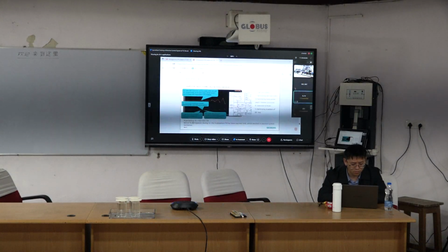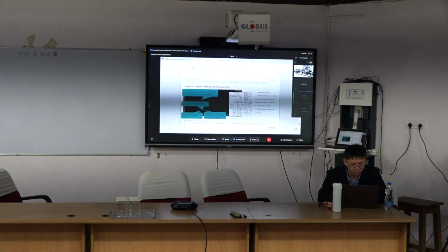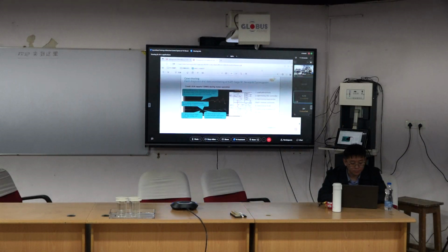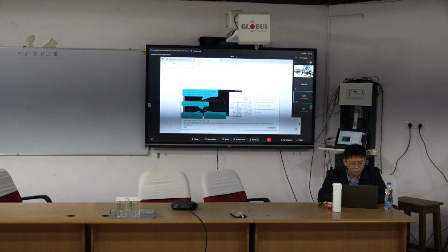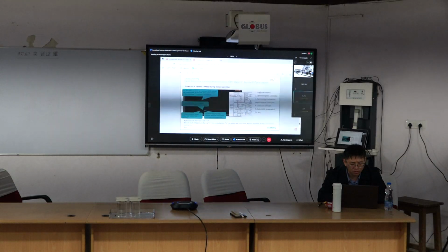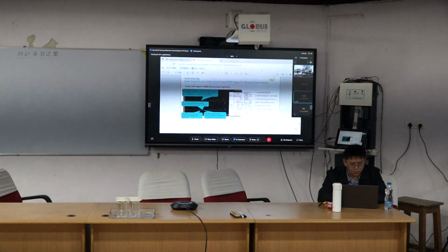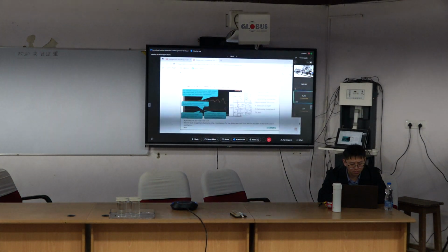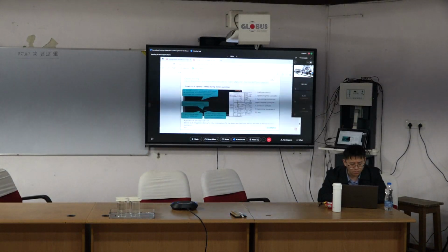Through analyzing the fault procedure, we can conclude there is no hardware fault. But the performance of the VDC controller is not good enough to match the load requirement of this link. So we give instructions to the customer. One, use load pre-control in the ALM. Two, optimize the PI controller.